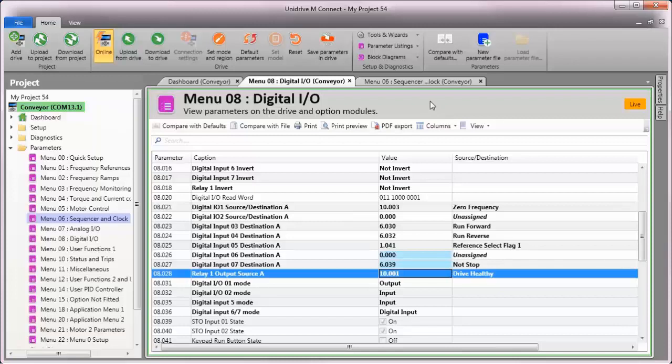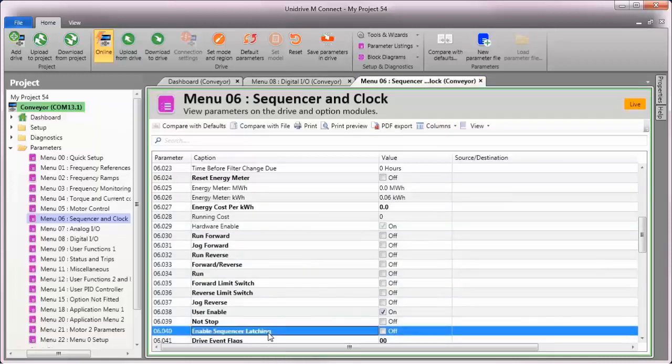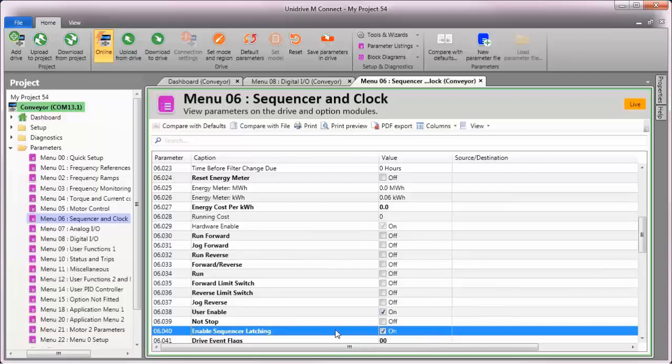To enable sequencer latching, I'll go back into menu 6 and have a look at parameter number 40. This is the sequencer latching. I'll turn this parameter on to enable the latching function.